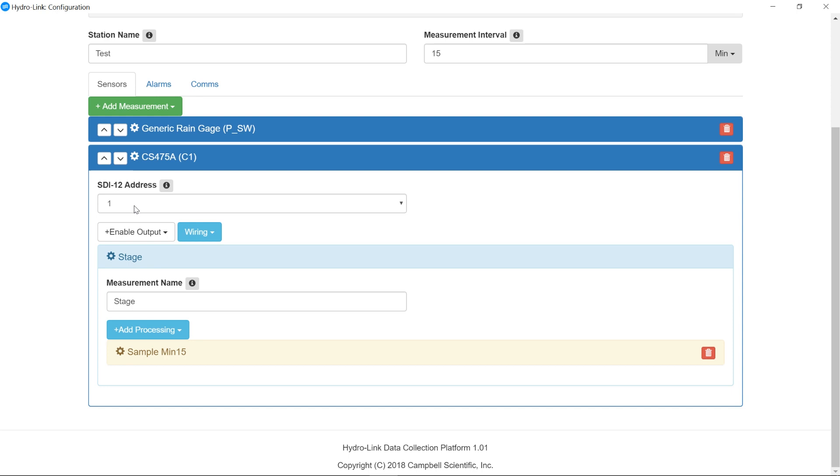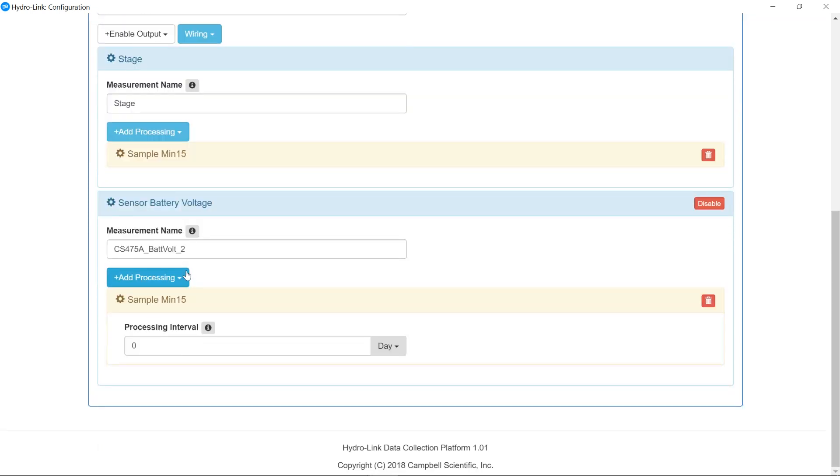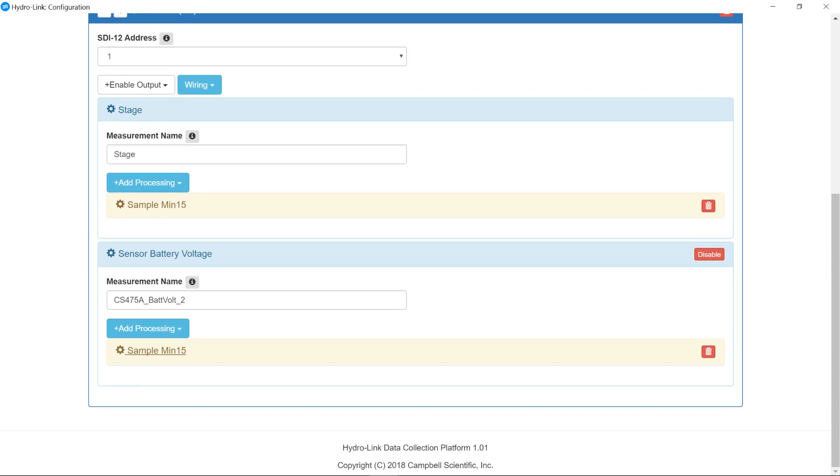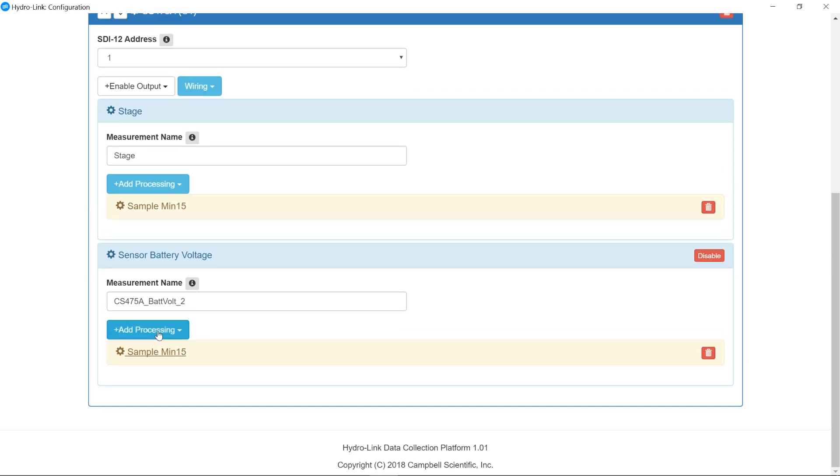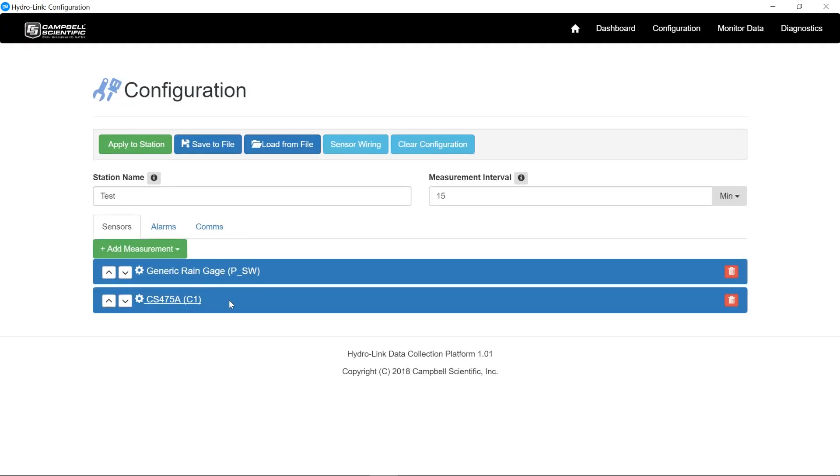So my radar sensor is enabled or is installed. I also know on this radar sensor, I have other options with it. So the first option or first parameter out of that SDI 12 sensor is stage, but it has three other parameters that can come out of it for a total of four. So distance, sensor battery voltage and an error code. So if this radar sensor was mounted on a bridge and several hundred feet away from the gauge, I may want to record the sensor voltage also. So I could easily bring that in and leave the processing to zero for an interval sample 15. And I have that set up now. So now on my radar gauge, I have it doing water and battery voltage, water level and battery voltage coming out of that radar gauge. If I want to change the order in which these are logged, I can easily just come down here and click this arrow and it swaps them.